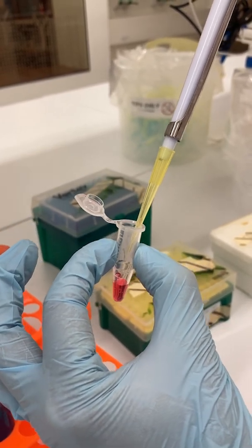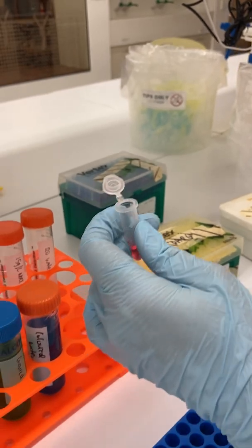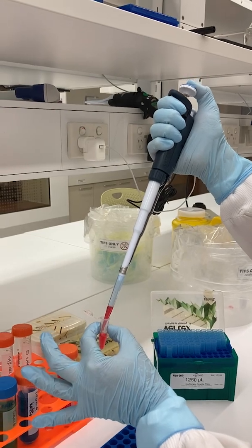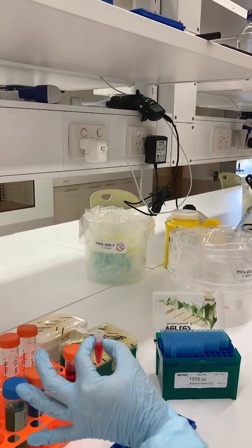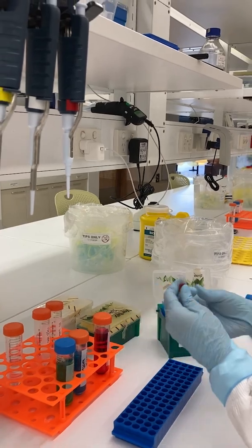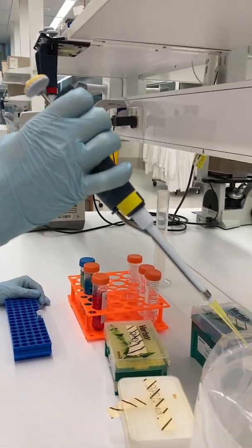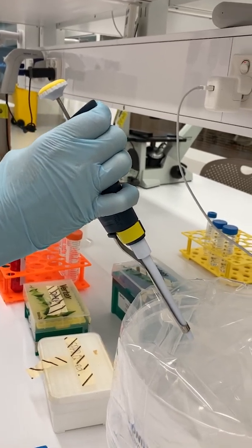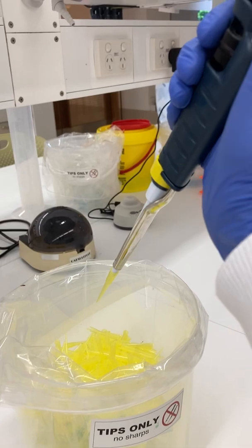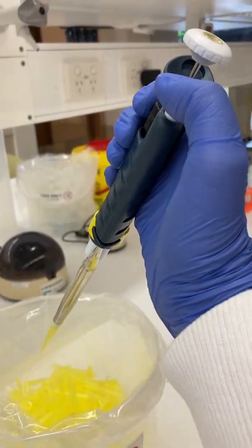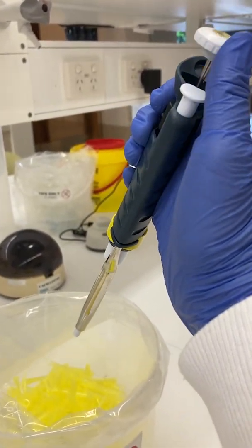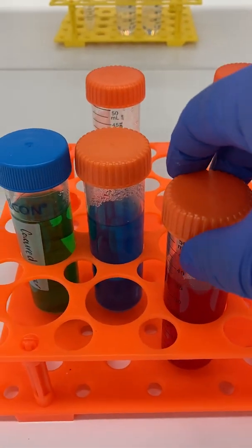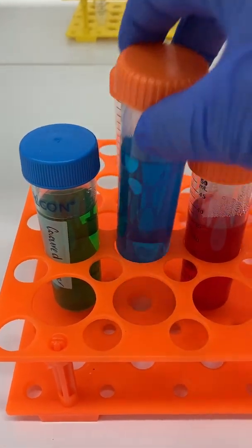If a droplet hangs at the end of the tip, touch the tip to the inside of the container. Remember to hold the plunger down until the pipette is out of the container. Otherwise, you may accidentally draw up the solution again. You must change tips between liquids and if it has touched any part of the container. To eject the tip, hold the pipette over a waste bucket and press the small ejector button on the side of the body. Repeat this process for each liquid you need to dispense.